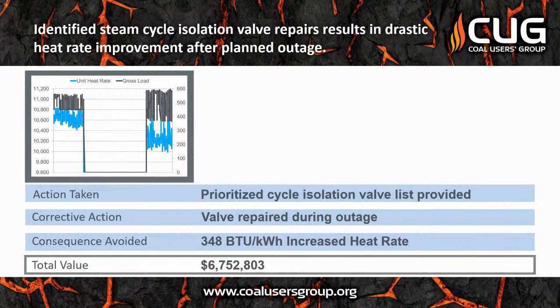In this case, we identified repairs needed to several cycle isolation valves. The repairs were completed, and the resulting improvement in heat rate was around 350 BTU per kWh.